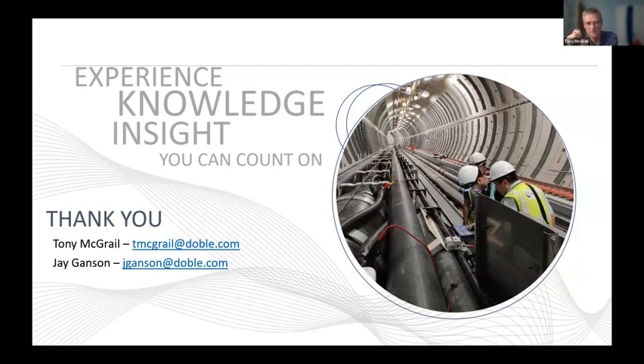We would find cables which are 80 and 90 years old come out of the ground, direct buried, and they look the same as the day they went in. And we find 40, 45-year-old cables come out of the ground and they look like they've been there for 1,000 years and they were still in very poor condition. So it's difficult to predict what condition a cable will be in without having a very good knowledge of its initial environment and how that environment will change. All right, bathtub curves.